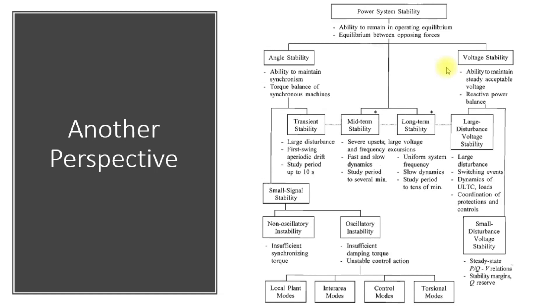If following a disturbance, voltages remain within permissible limits, it means that we have achieved voltage stability. These stabilities can be either large disturbance, transient, midterm, or long term. Transient stability refers to large disturbances or three-phase faults close to the generator — something very swift that can happen to the system. Large disturbance voltage stability involves a single line-to-ground fault or three-phase fault on the load side causing huge variation in voltages.